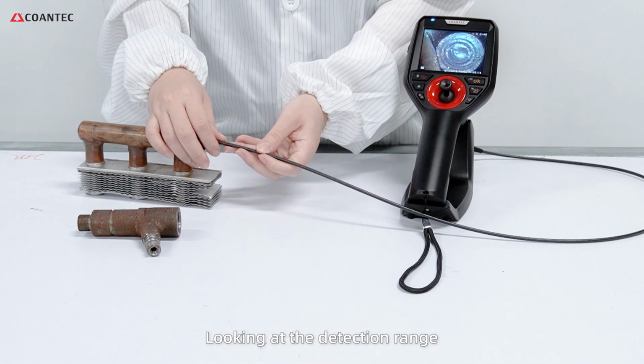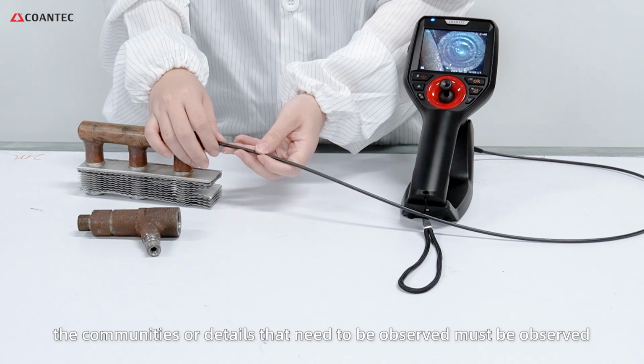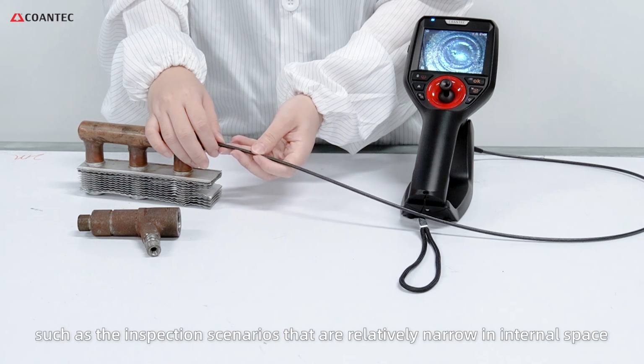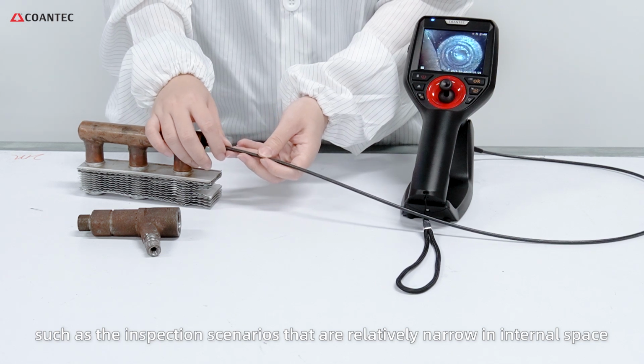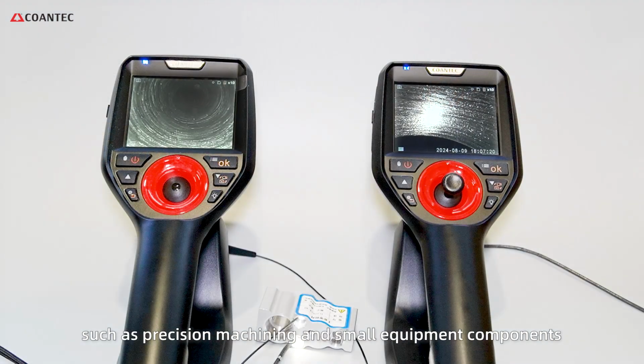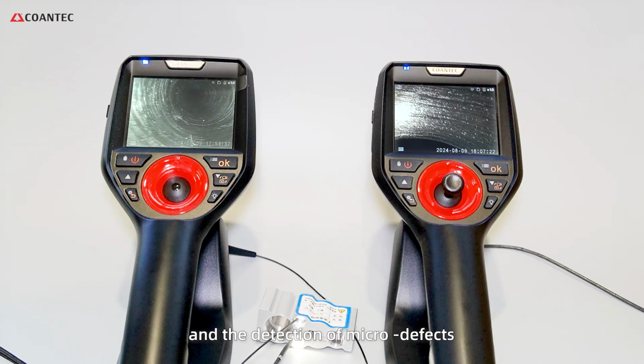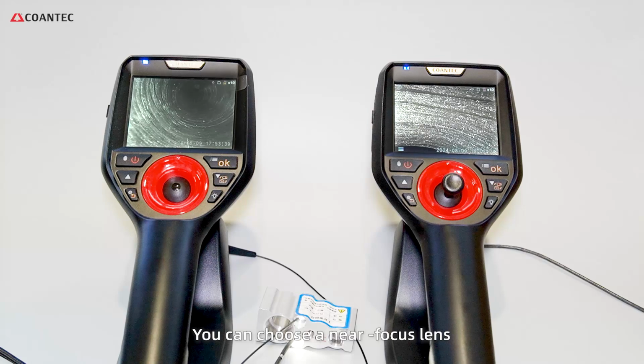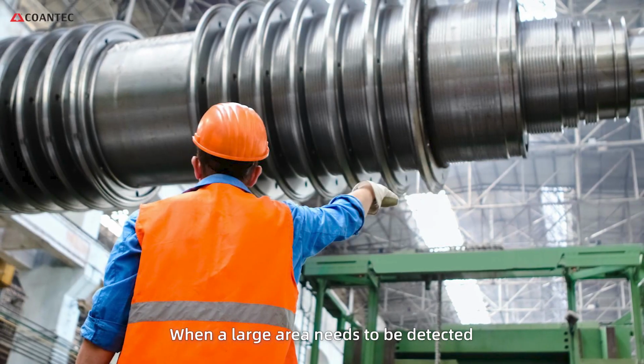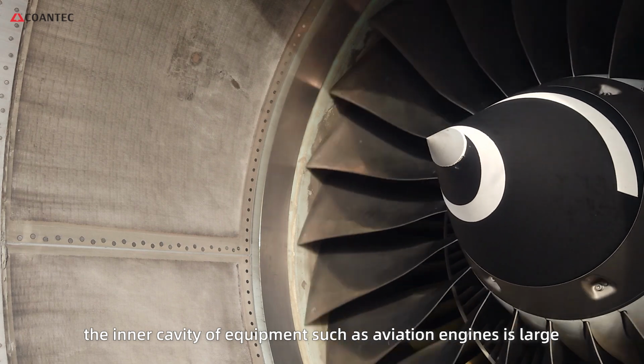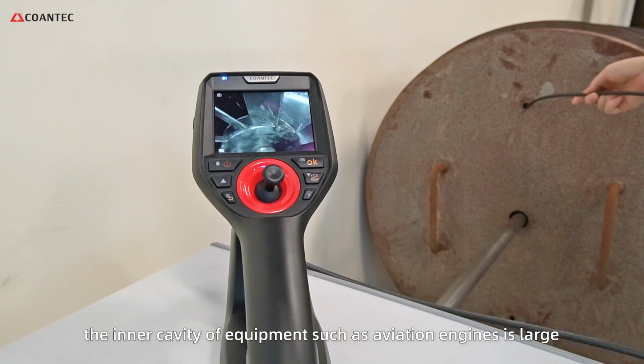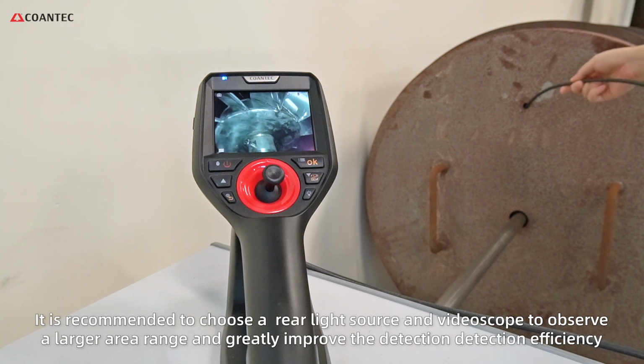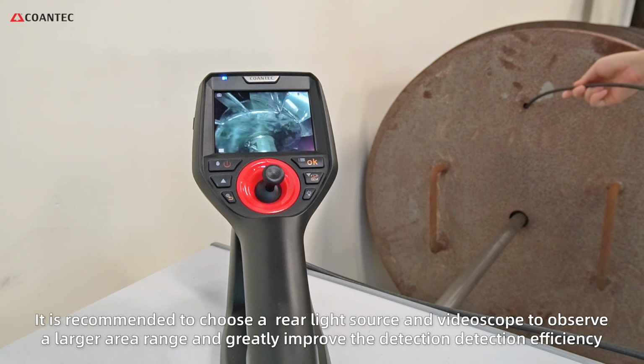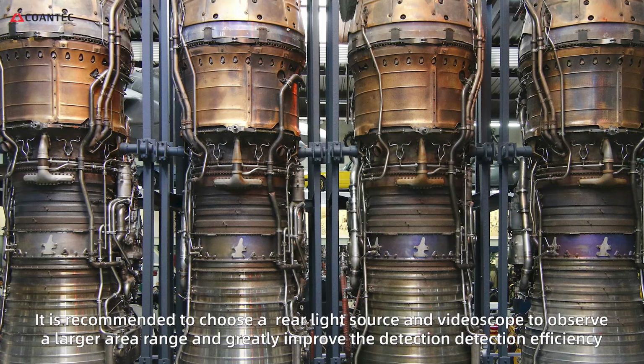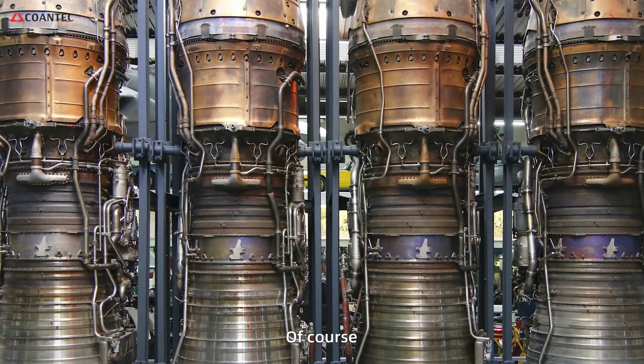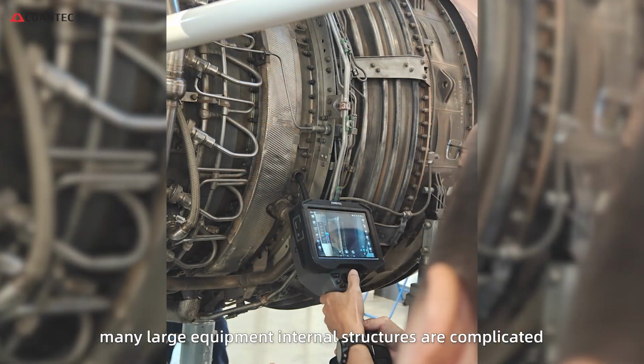Looking at the detection range, you must consider the areas or details that need to be observed, such as inspection scenarios with relatively narrow internal space, like precision machining and small equipment components, and the detection of micro defects. You can choose a near-focus lens. When a large area needs to be detected, such as the inner cavity of large equipment like aviation engines, it is recommended to choose a rear light source videoscope to observe a larger area range and greatly improve the detection efficiency. Of course, many large equipment internal structures are complicated.